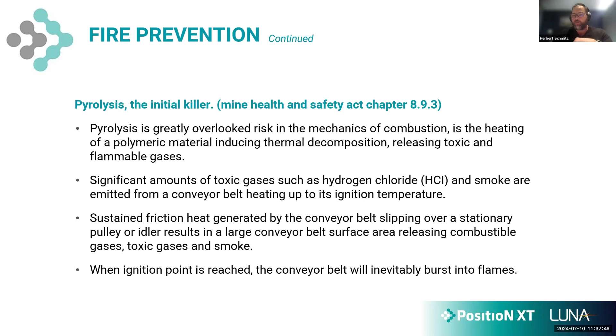By the time we're detecting a fire, it's already too late. And the reality is, the majority of fire detection technology used within existing conveyor installations is exactly that, fire detection. Any heat detection cable needs to be exposed to extreme temperature or a flame to make contact. Flame detection, that's pretty obvious. It's already on fire. Carbon monoxide monitoring, very typical in underground mining operations. Carbon monoxide is a byproduct of combustion, hence there's already a fire. And fire sprinklers are potentially the slowest form of fire detection within a conveyance infrastructure.